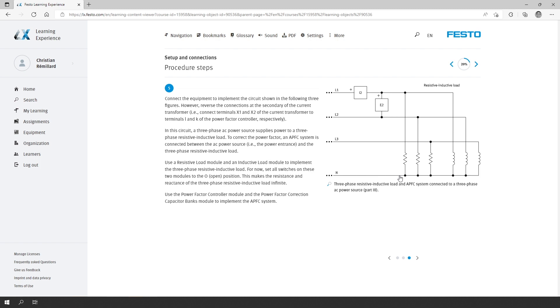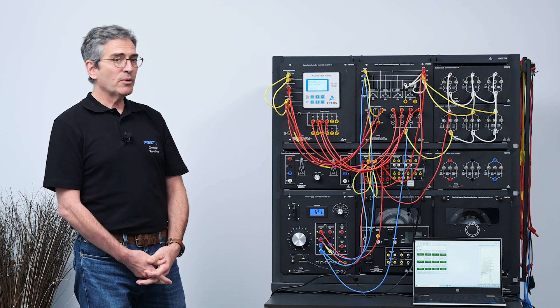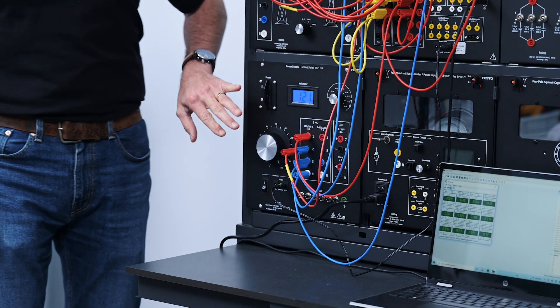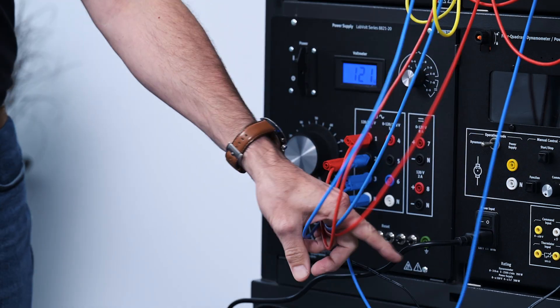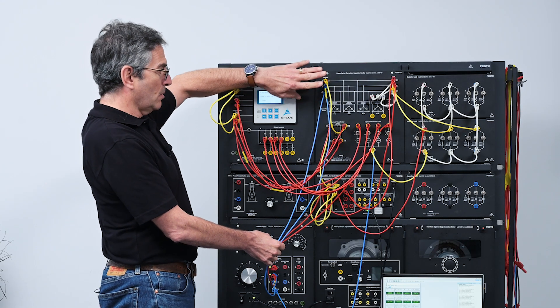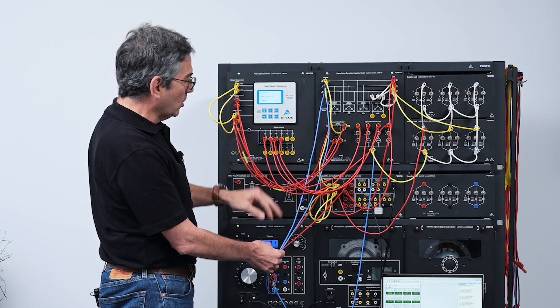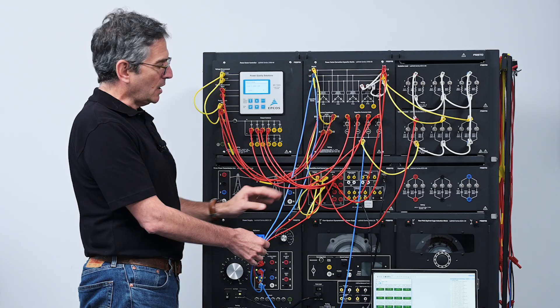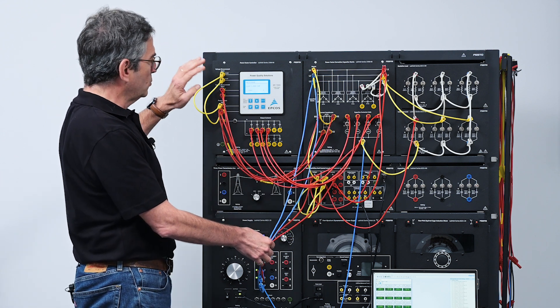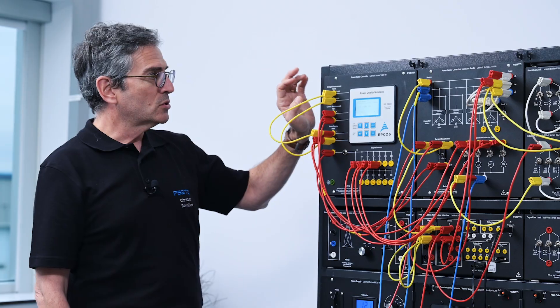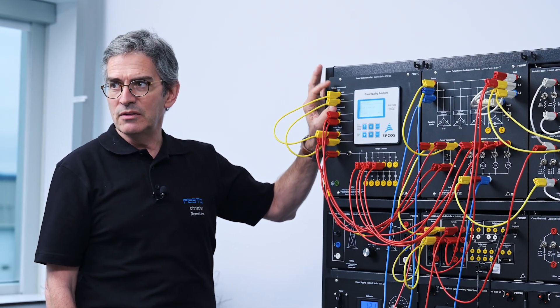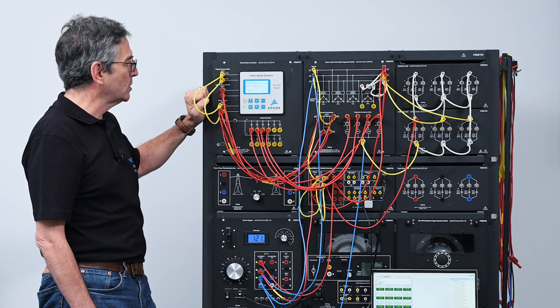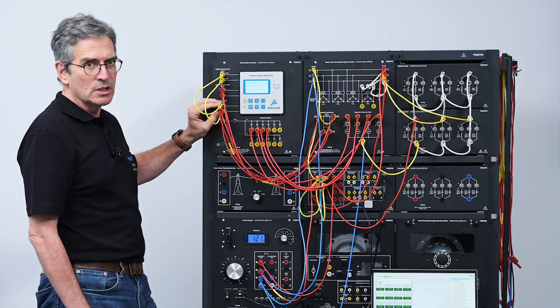Now let's go back to the system itself, having a look at the connections and testing the system. Starting from our three-phase power supply down here, we simply go all the way up to our capacitor bank. We also go first through our data acquisition module to be able to measure the voltage and current on the source side of our system. Then we do all the connections to the power factor controller module itself.